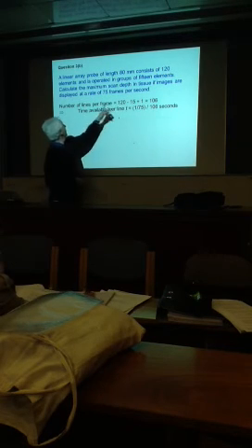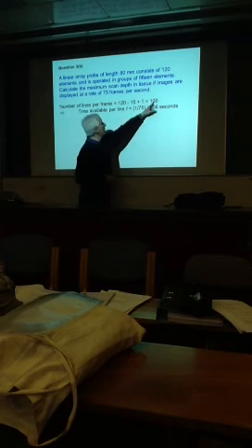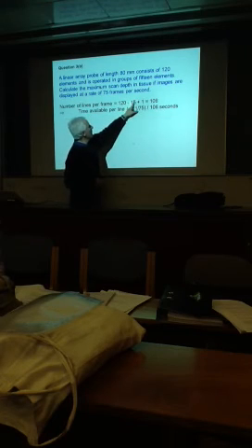Well, first of all, calculate the number of lines in the frame, in each image. Well, we have 120 elements. They're pulsed in groups of 15. Therefore, the number of lines in our image will be 120 minus 15 plus 1, or 106. Should be able to calculate that very easily. So the first one is going to be 1 to 15, the second one is going to be 2 to 16, and so on. And the last one is going to be 106 to 120. Therefore, there must be 106 lines in the image.